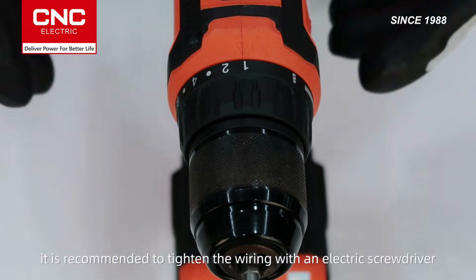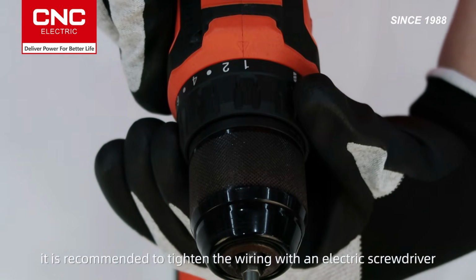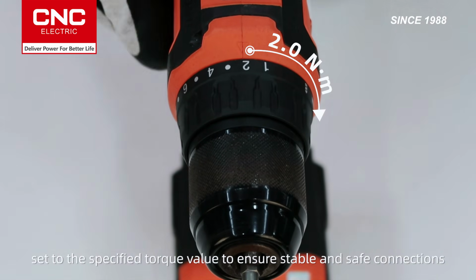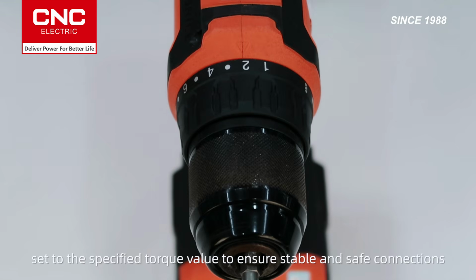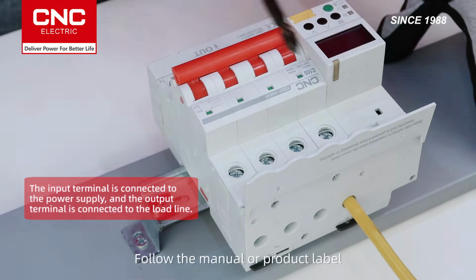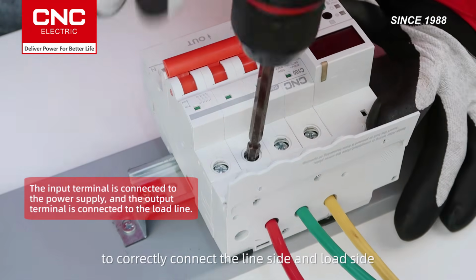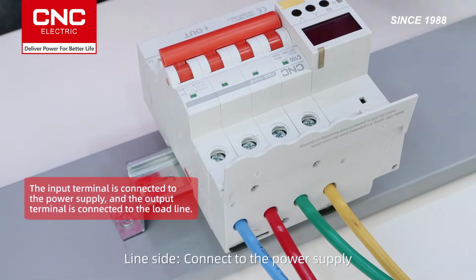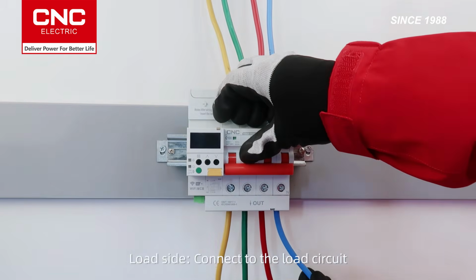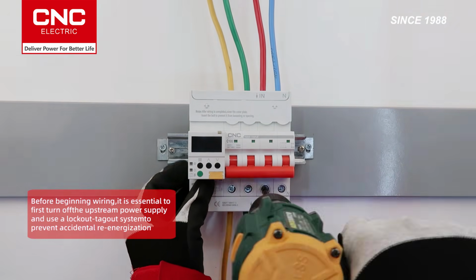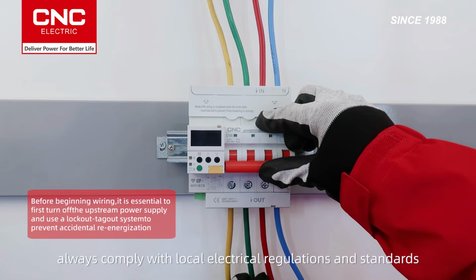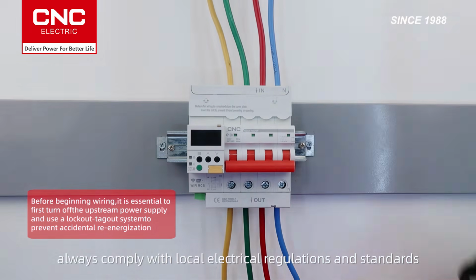Finally, it is recommended to tighten the wiring with an electric screwdriver, set to the specified torque value to ensure stable and safe connections. Follow the manual or product label to correctly connect the line side and load side. Line side, connect to the power supply. Load side, connect to the load circuit. During wiring, always comply with local electrical regulations and standards.